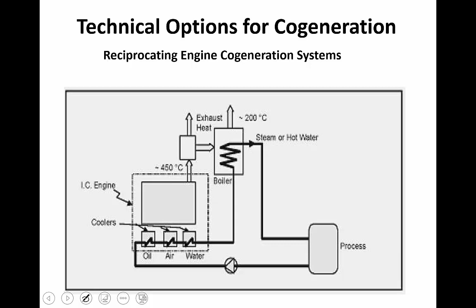The base electrical load matching means that in this configuration, the cogeneration plant is sized to meet the minimum electricity demand of the site and the historical demand curve. The rest of the needed power is purchased from the utility grid. The thermal energy requirement of the site could be met by the cogeneration system alone or by additional sources. If the thermal energy generated with the base electrical load exceeds the plant demand, and if the situation permits, excess thermal energy can be exported to neighboring customers. Okay, this is one factor.